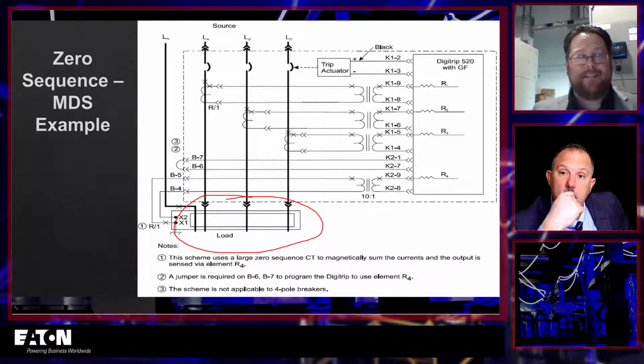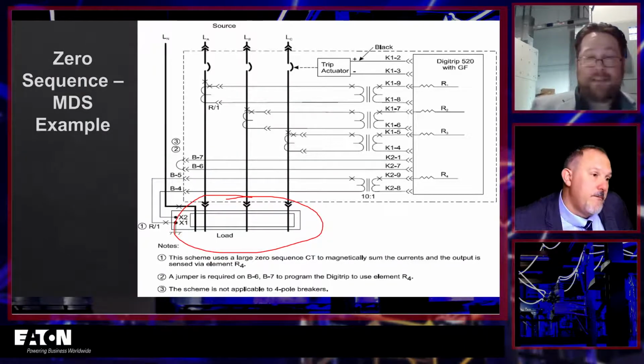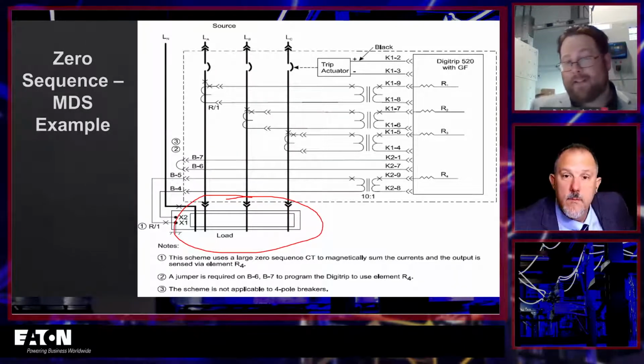Now you would say that can't happen, and how did it happen? And the switchgear was in service for a few years before anybody even figured this out. That's why this testing is so important, to make sure you have, like you said, qualified individuals that don't just understand the breaker, but the system overall, all the different components. Do those tests from the start to confirm that mistakes weren't made in the design process, in the manufacturing process, shipping a switchgear.